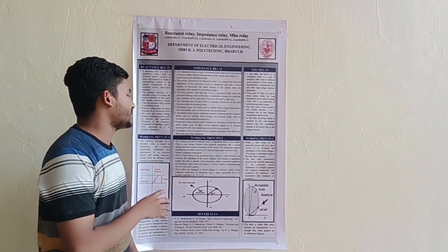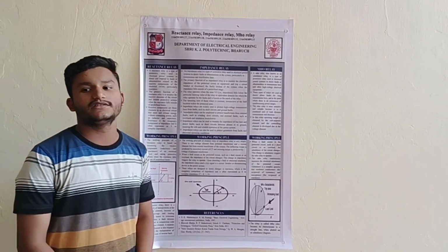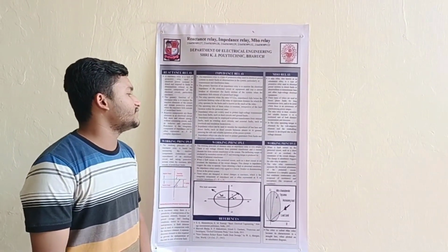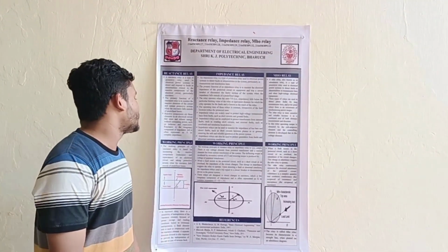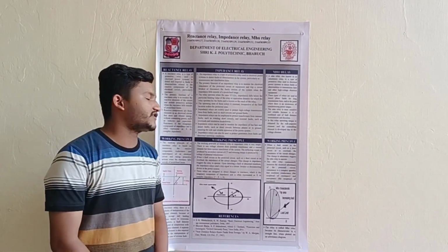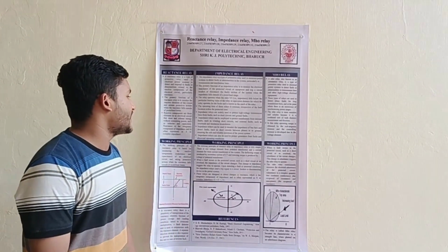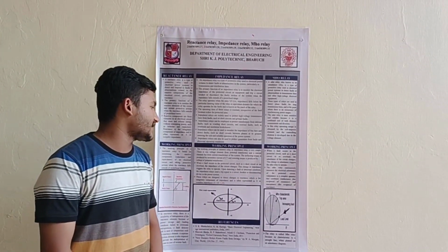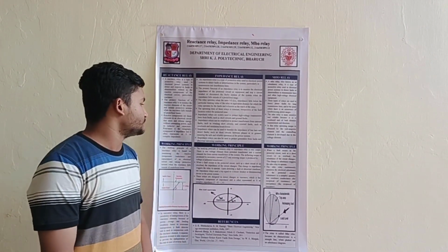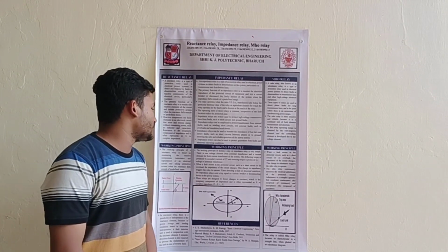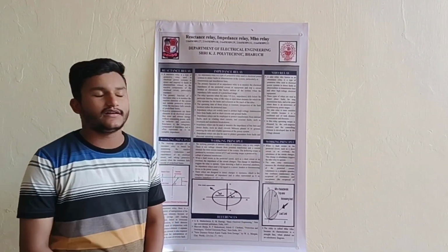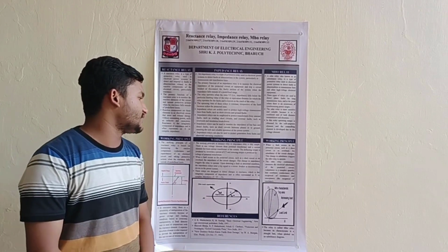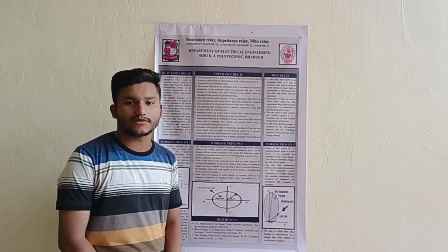Impedance relay working principle. The working principle of distance relay or impedance relay is very simple. There is a one voltage element from potential transformer and a current element fed from current transformer of the system. The deflecting torque is produced by secondary current of CT and restoring torque is produced by voltage of potential transformer.